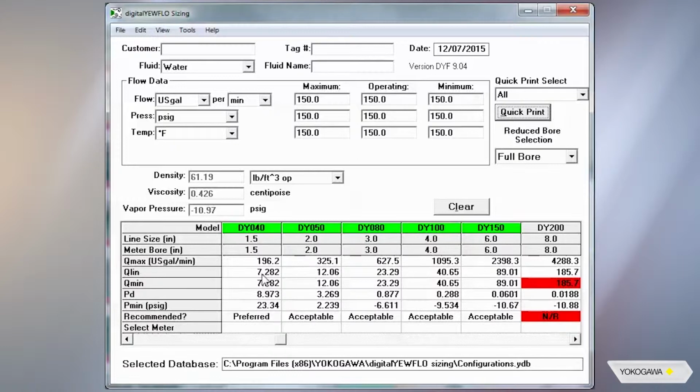The reason is because it meets the 150 and you still have some gap that the unit can go up. If you're planning in the future to see a higher flow, then you can move to the next unit that would allow you to go up to 325.